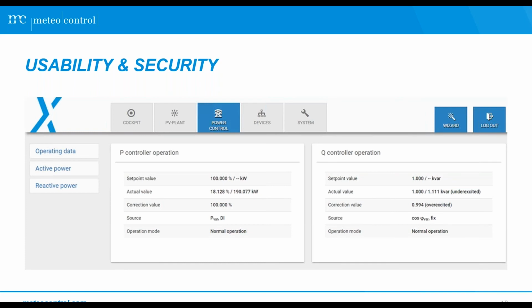A good thing here again, what you see on the picture is the overview. You see all the power control values live, in real time - the set point, the measured value, and the corrected value. So you know exactly what the controller is doing, and the mode, of course. You can see all the set points as well, which is required very often for the calculation to be able to explain that it was power control and not a loss.